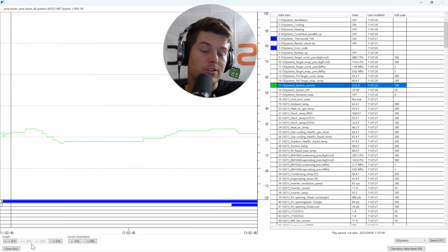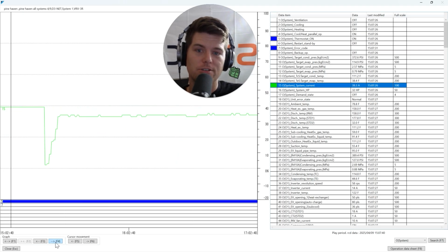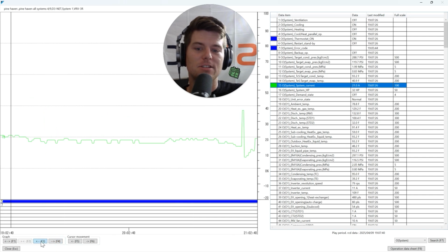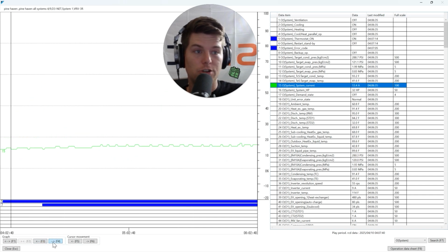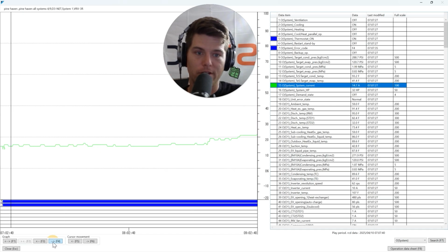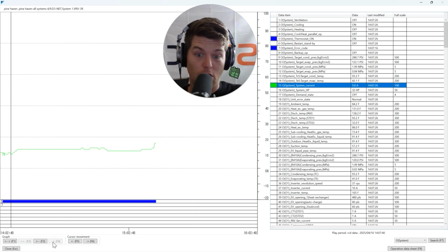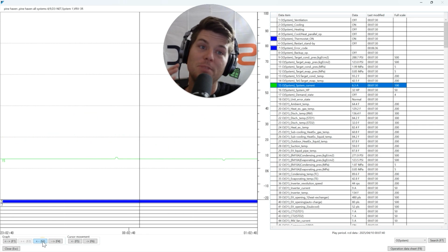Now, something fun to do, in your spare time, in your leisure time, 'cause you get so much time, is populating system current amps. And sometimes you can just go through the data set, and this is 28 hours, just so you know, and you can see some crazy high spikes. Remember that the energy usage you see here on system current is the total amount of current for all three modules for VRV3. And when we see those large giant spikes, and I don't see anything too crazy, but sometimes it's fun, use that term very loosely here.